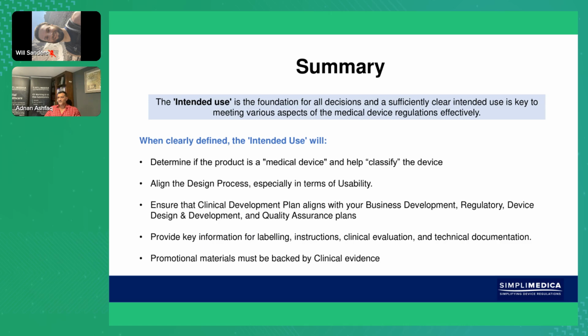In summary, the intended use is the foundation for all decisions, and a sufficiently clear intended use is key to meeting various aspects of the medical device regulations effectively. When clearly defined, the intended use will, number one, determine if the product is indeed a medical device, and will also help you classify the device. Is it class 1? Is it 2? Is it 3? Is it implantable? If it's implantable, it pretty much wouldn't be a class 1. So we can kind of dodge that.